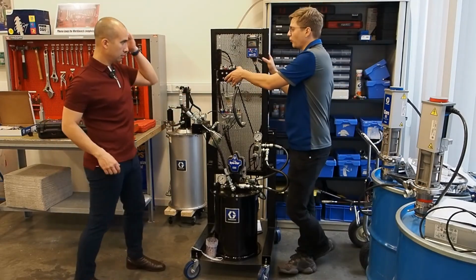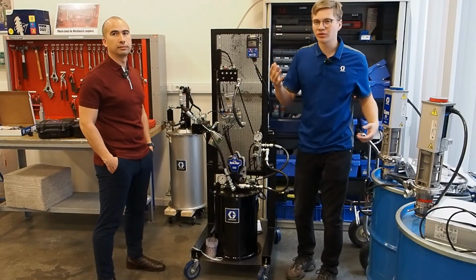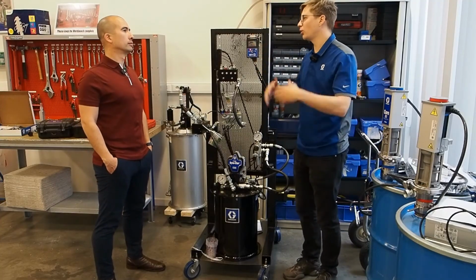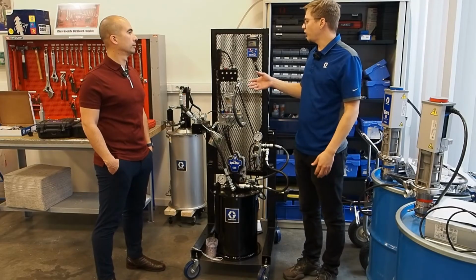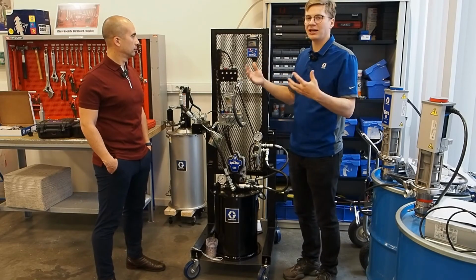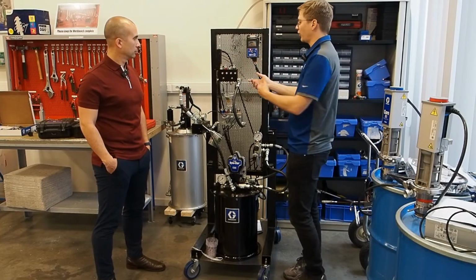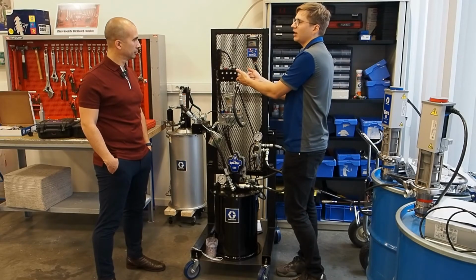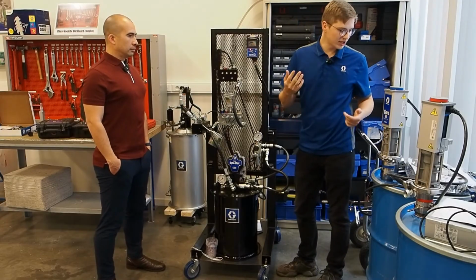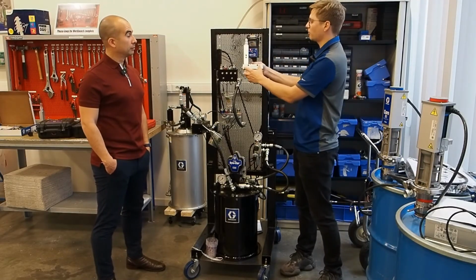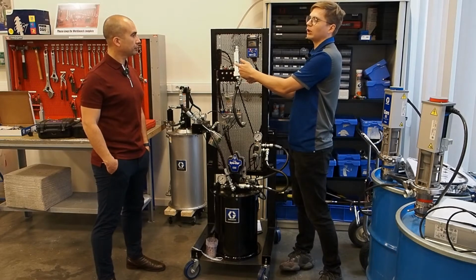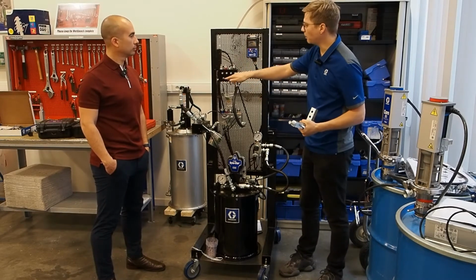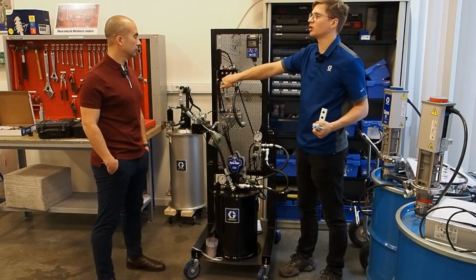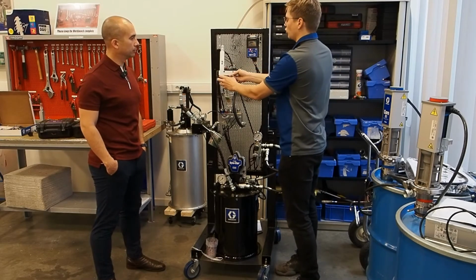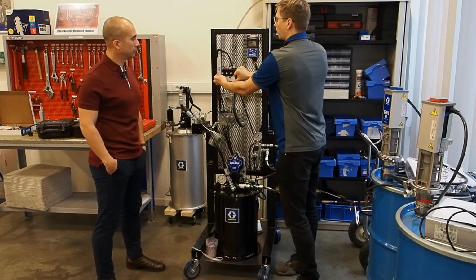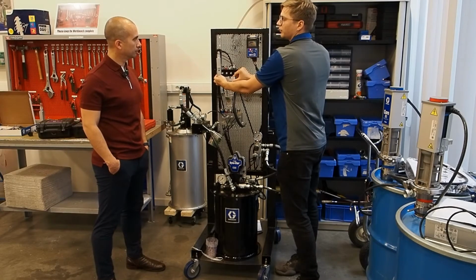We also made this manifold because we call them legacy injectors, since these round and rectangular injectors are all over the industry. That's why, even for customers who want to experience the benefits of the cartridge technology, we made the threads the same, for example the inlet, the same 3/8 NPT as your legacy injector. So it's the same manifold like this, where your injectors are mounted, the same thread here, the same 1/8 NPT outlet. Even the mounting bolt pattern is the same as the legacy injectors, which is here, you see. So I can easily drop in the cartridge manifold and replace the legacy manifold.